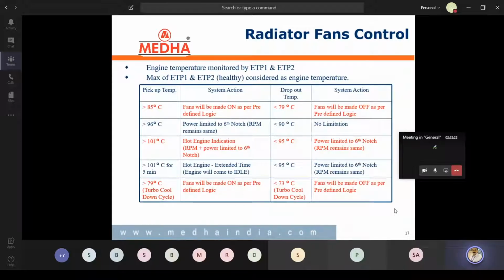If the temperature is still not in a decreasing or stopped trend, and is still increasing, then number two fan also runs at slow speed by operating the contactor. Further, again it will monitor for 20 seconds. If the temperature is still not decreasing in trend, then number one fan goes to high speed. After 20 seconds, again number two fan also goes to high speed. Like that, there is a predefined software logic. As per that it goes to run.